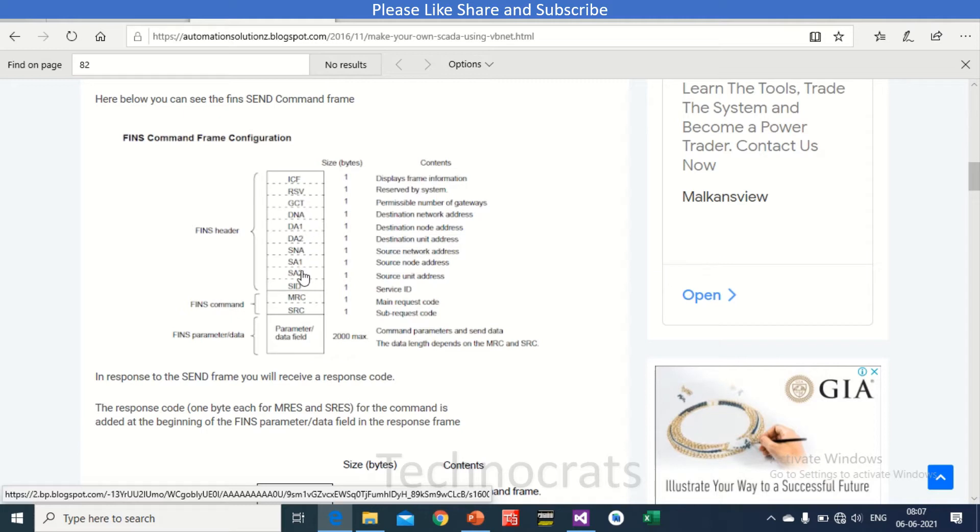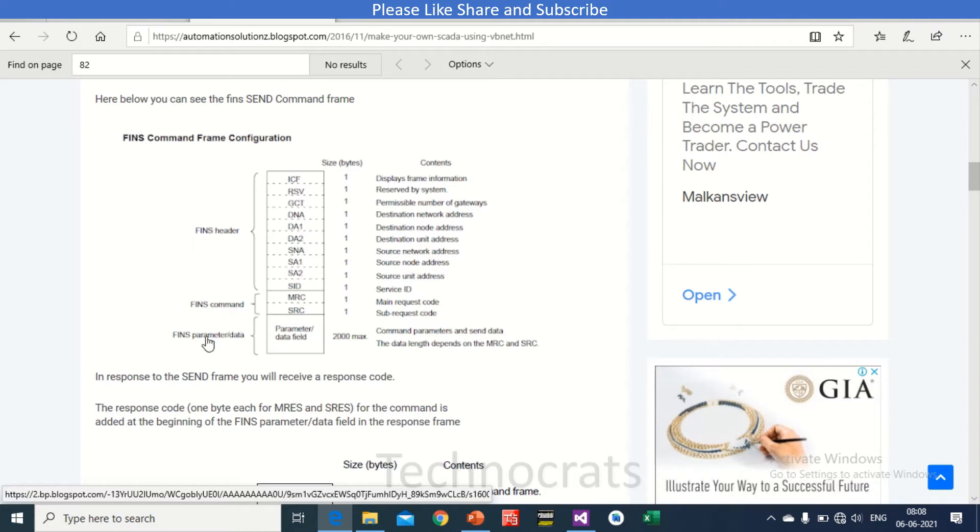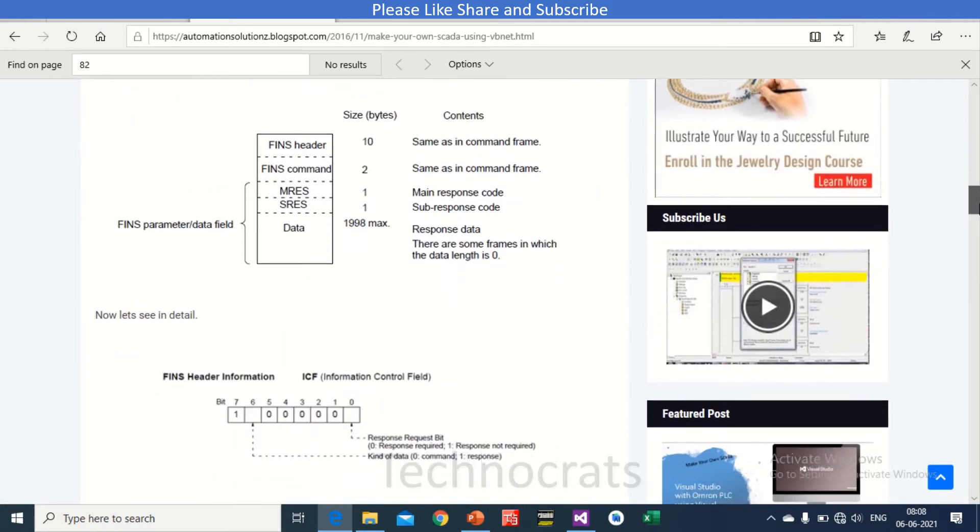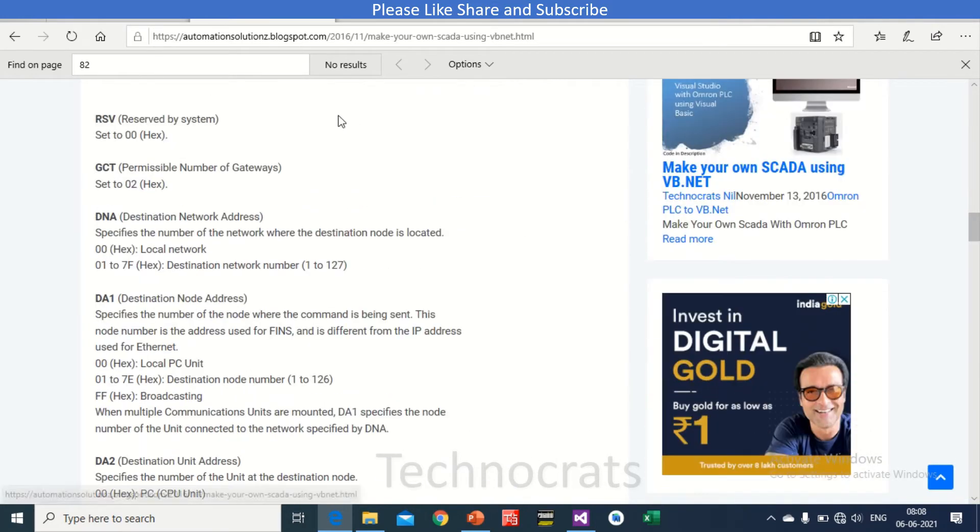This is basically the above FINS header: ICF, RSV, GCT, and DNA, DA1. All these are, you can see the content here, display frame information, reserved by system. RSV is reserved by system, so all these are one-time adjustment parameters. The other is FINS command. This can be changed according to your need, data if you want to read D register or you want to write D register or you want to read CIO bits or you have to write CIO bits. So the FINS frame will change accordingly and also the FINS parameter data.